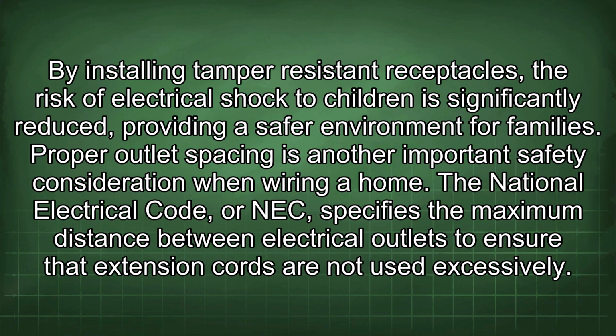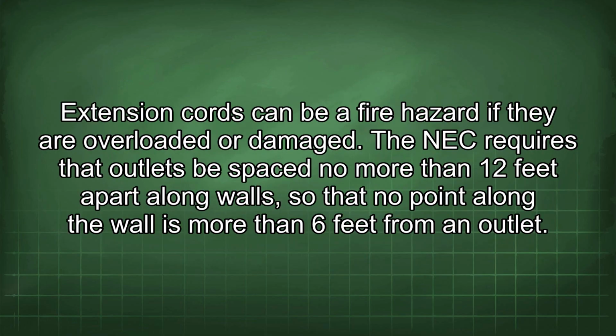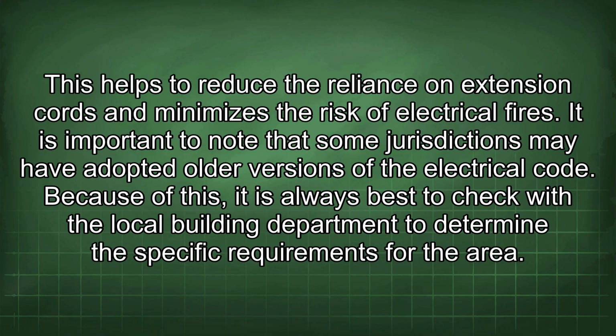Proper outlet spacing is another important safety consideration when wiring a home. The National Electrical Code, or NEC, specifies the maximum distance between electrical outlets to ensure that extension cords are not used excessively. Extension cords can be a fire hazard if they are overloaded or damaged. The NEC requires that outlets be spaced no more than 12 feet apart along walls, so that no point along the wall is more than 6 feet from an outlet. This helps to reduce the reliance on extension cords and minimizes the risk of electrical fires.